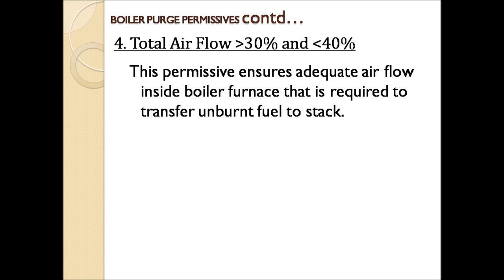The fourth boiler purge permissive condition is total air flow should be greater than 30% and less than 40%. This condition ensures adequate air flow inside the boiler furnace, which is required to transfer unburnt fuel to the stack or chimney. As discussed earlier, if air flow is less than 30% then the MFT condition will be true, and we cannot go for boiler purging. So for boiler purging, air flow must be maintained above 30% and less than 40%.